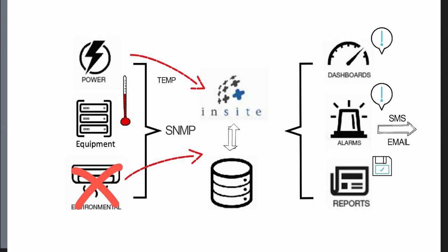And then lastly, we can add in control functionality. If we have control panels available to the engineers who may be seven floors up, in a different facility, or down the road, they can actually start doing some power shedding to reduce the processing load. They can set up a salvo that turns off all the outlets for non-essential equipment, so you're not generating more heat than you need to, giving the essential equipment much more of a chance to keep running under this abnormal situation. And again, all of this is being logged into the database. Everything that happens is reported as and when it needs to, so it can be inspected later on.